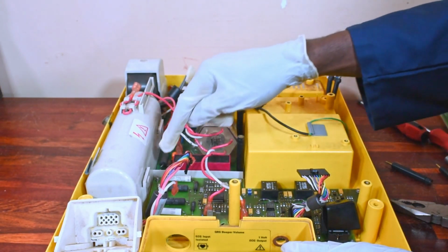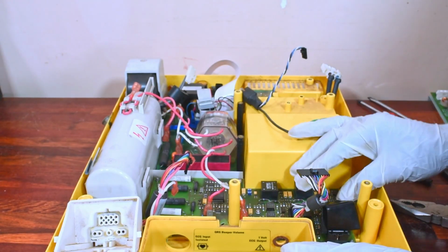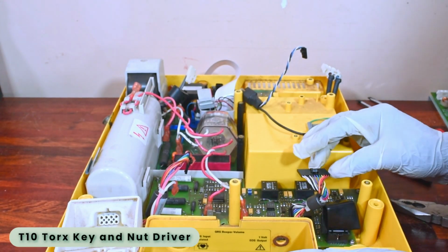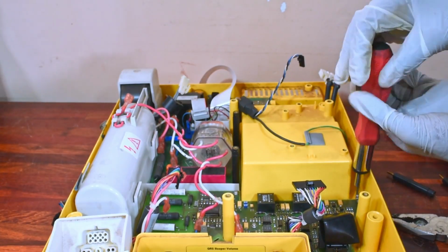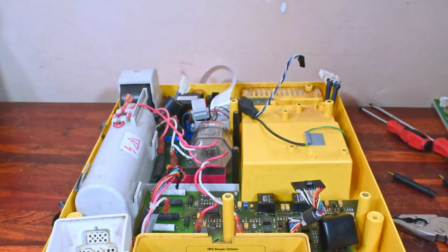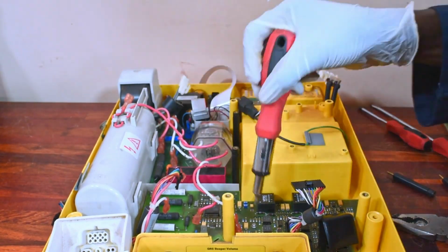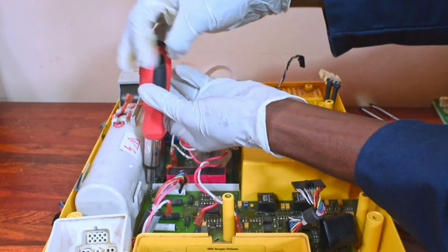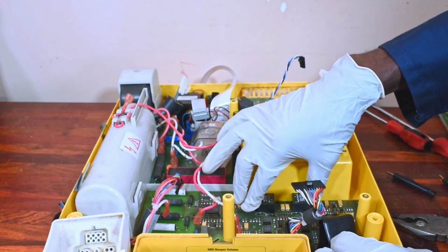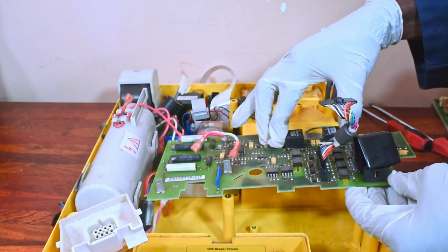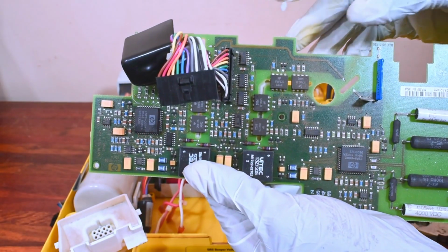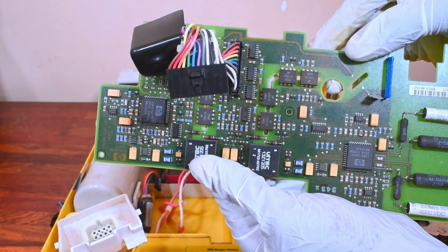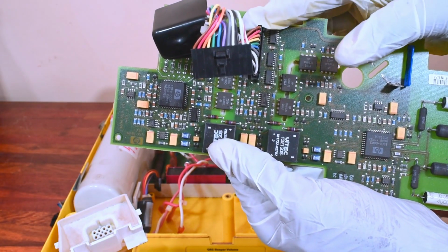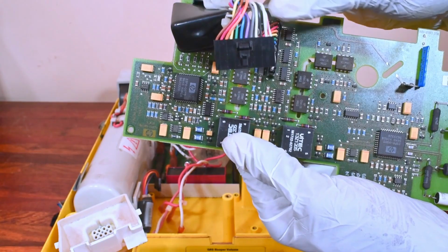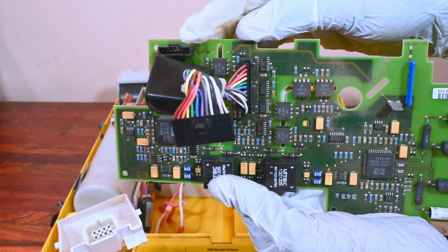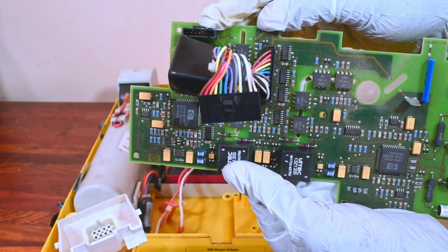The next step involves removing the 5 screws that secure the board using a nut driver and a T10 Torx key. So right here is the ECG front-end control board. And this one is the connector for the cables that run between this control board and the main control board. And over here is the ECG input connector.